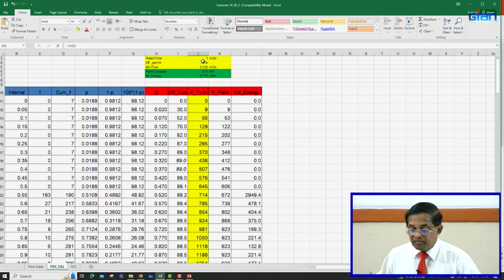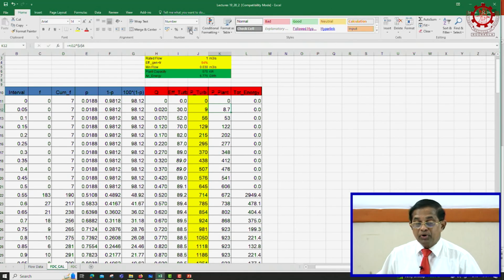Now, we put a value here, generator and transformer efficiency as 94%, right. So, we multiply the turbine output with 0.94. This number has not changed because of the decimal places, it is 8.7 really, because 9 into 0.94, and the next one is 56 into 0.94, which is 53 kilowatts plant output, 129 into 0.94, 122, right. So, this is really at the terminals of the transformer after stepping up, the available power to be connected to the grid, right.